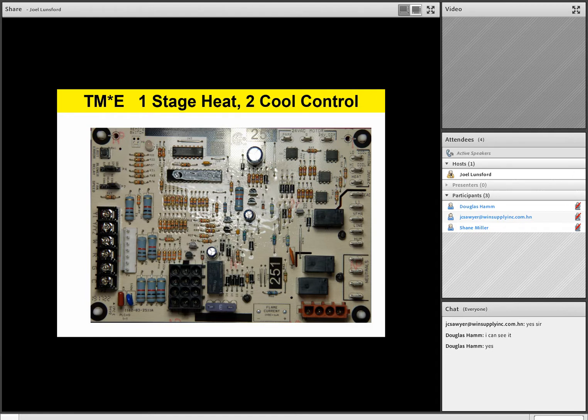And please, by the way, if you do have a question midpoint or through this next slide, just unmute your mic and go ahead and ask that good question, and we'll be glad to answer it for you as we look at every input and every output on this control. So this is a single stage heat, two-stage cool capable control board featuring a high efficiency ECM motor product. Starting out at the lower left-hand corner, you're going to see some low voltage terminals.